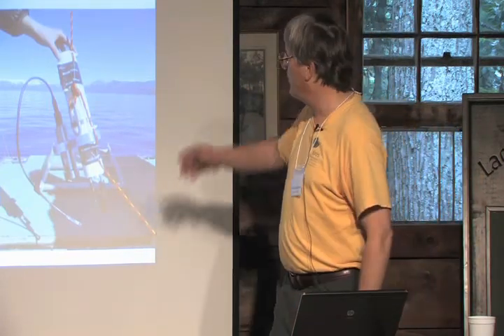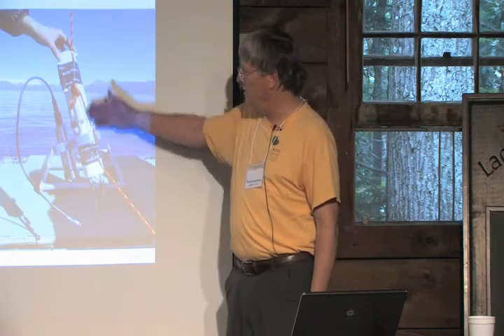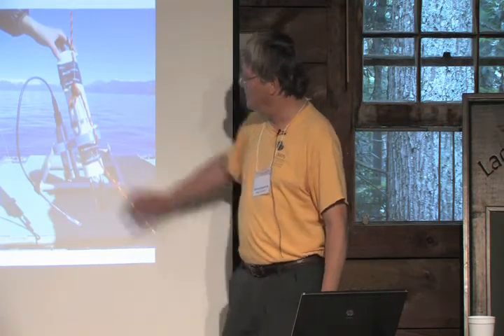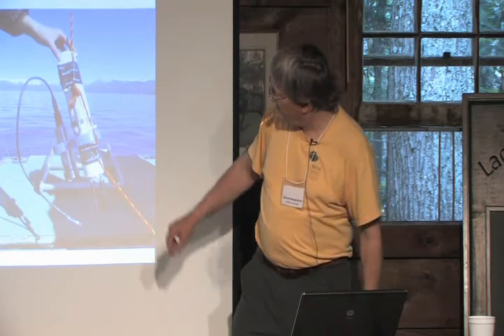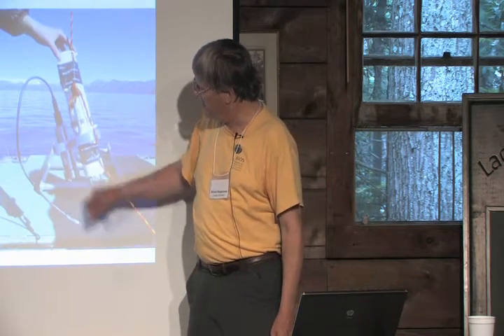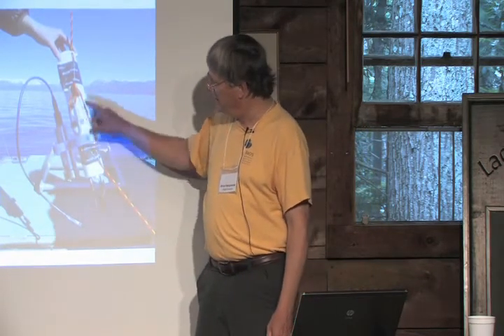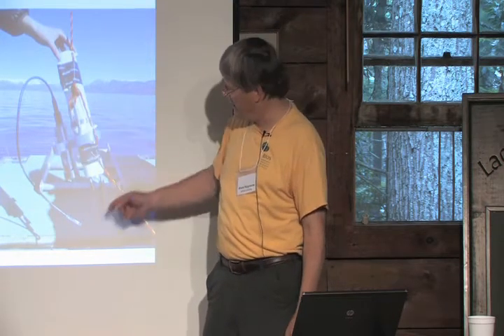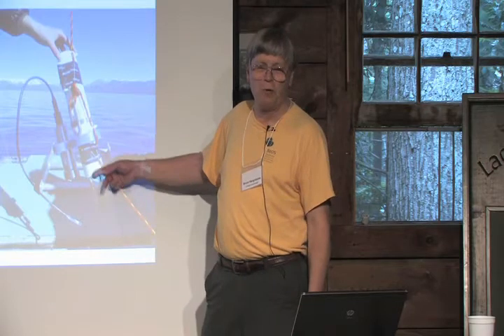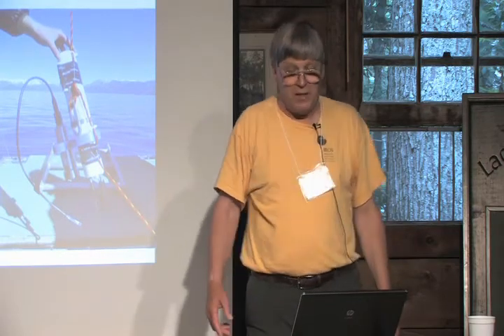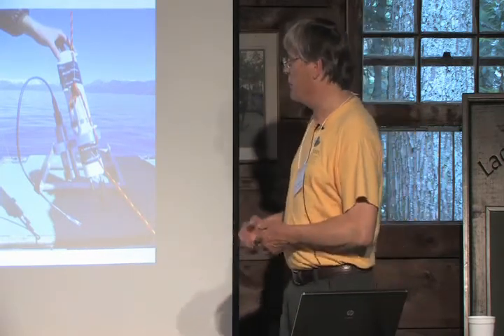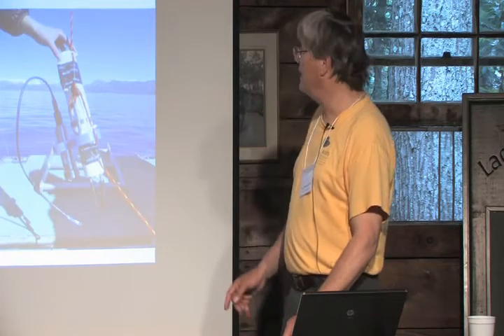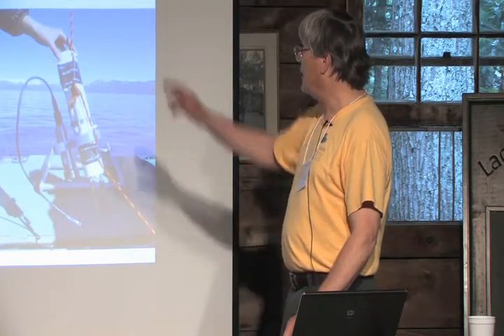So this is where we're deploying it to 465 meters in Lake Tahoe. It's a big thing there. The sensor membrane is on the face, and in the case of RBR Global, they don't use the temperature sensor that's built in here to report temperature. They have a fast responding probe over here. But the internal compensation that's used to generate percent saturation in the Rinko uses its own temperature. So there's a possible question, if you're using it for profiling, that they get out of sync.